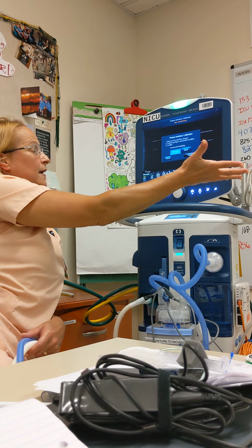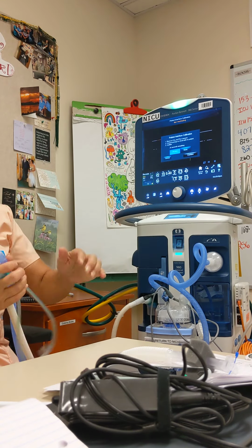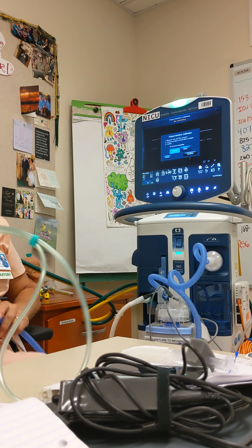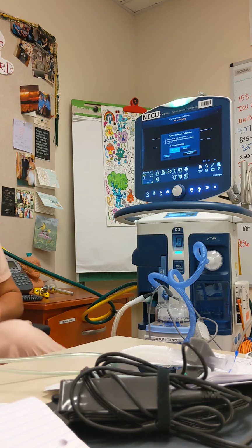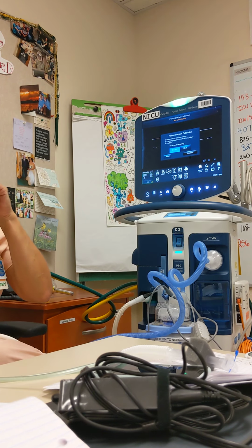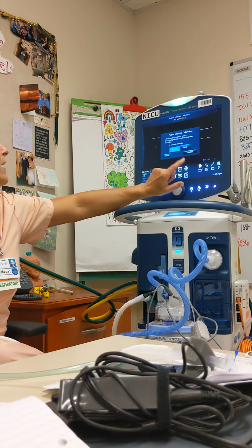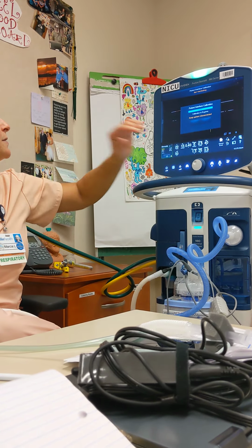So that's why it's saying that we will not have those two on there. Then you would connect whichever you're using, and I am going to assume it's going to be these. You are supposed to lay this down as if it would be on a patient, similar to this. Don't let it be hanging on the ground or just hanging off the vent. Hit your prong or your mask, and now it's going to be 2 minutes.